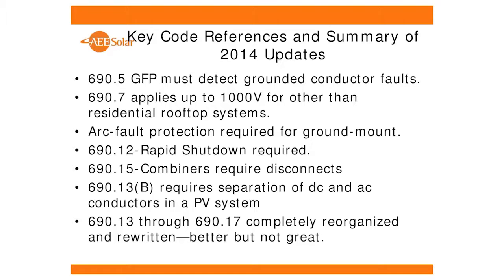690.15 requires disconnects on combiners, so that was a new requirement. Now the reality is that most combiners out there today do come with at least a disconnect option, but that was a requirement that went in the 2014 code. And 690.13(B) requires separation of DC and AC conductors in a PV system. So this was a big change.